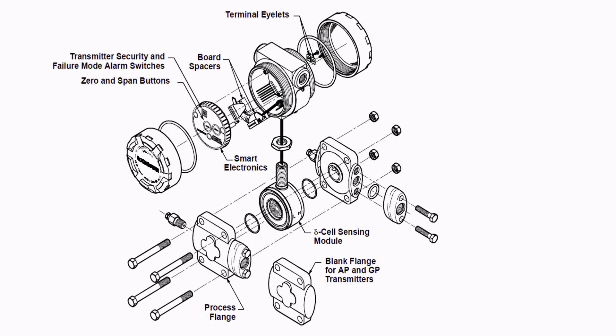Next we have the sensor module. You can see very clearly that at the bottom it has a diaphragm and it has both HP and LP connections — you can see both process flanges are available. In between we have the sensor module which has a diaphragm. The pressure exerted into the process flange pushes the diaphragm, which has a silicon fill fluid, and that pushes the sensing diaphragm. That displacement signal is sent to the smart electronics, which senses the displacement and converts it into a 4-20mA electrical signal.